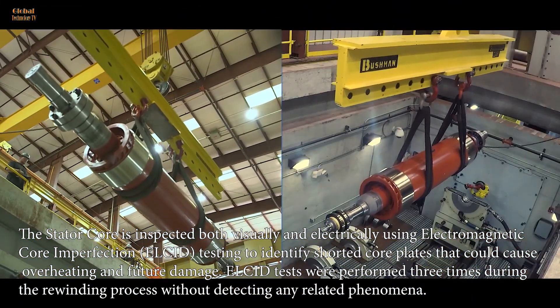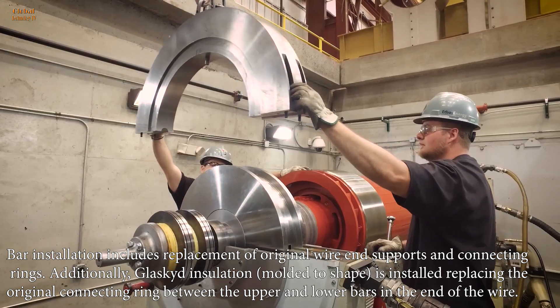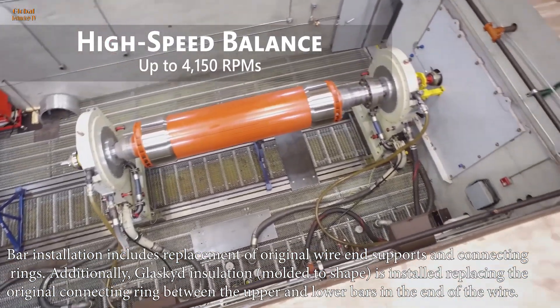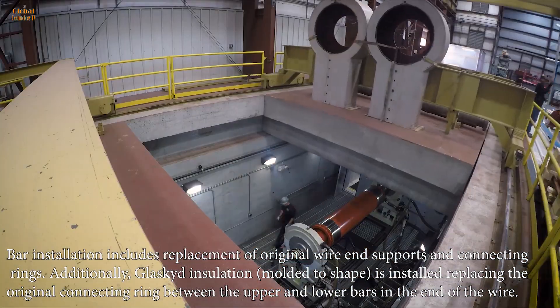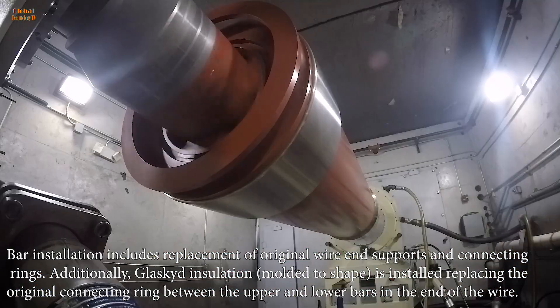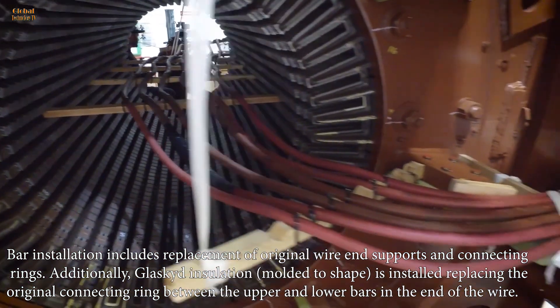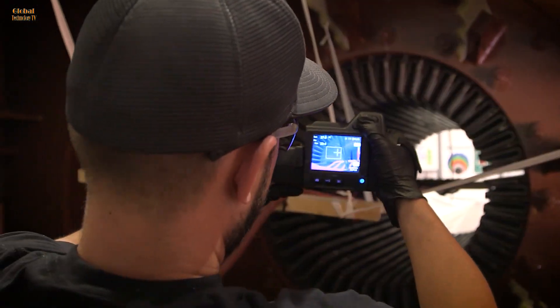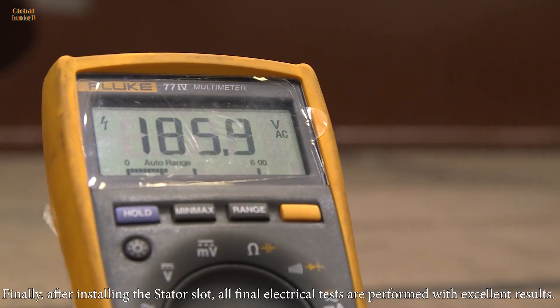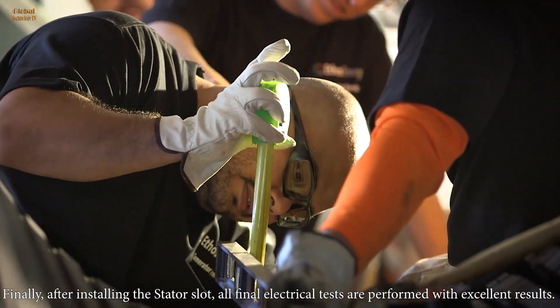Bar installation includes replacement of original wire end supports and connecting rings. Additionally, Glaskyd insulation, molded to shape, is installed replacing the original connecting ring between the upper and lower bars and the end of the wire. Finally, after installing the stator slot, all final electrical tests are performed with excellent results.